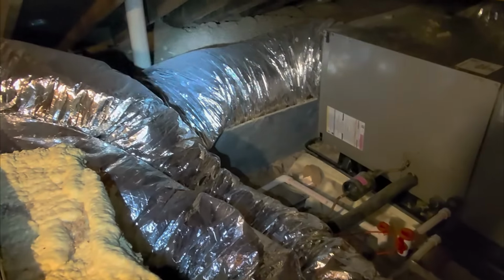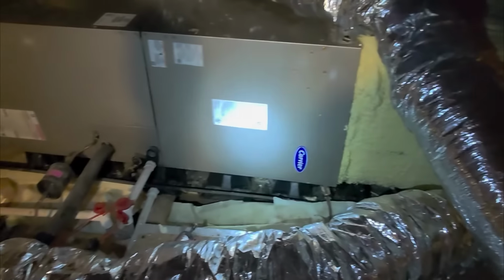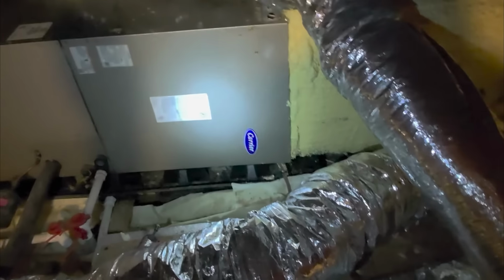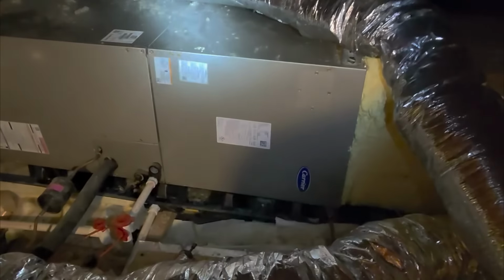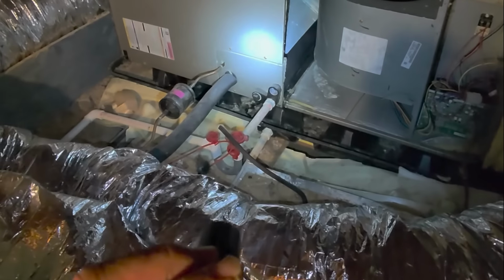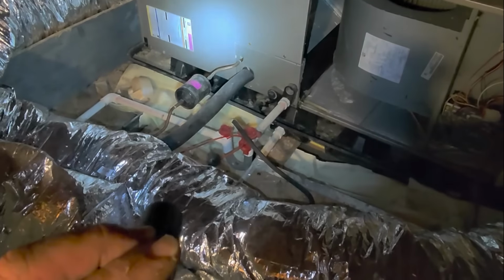And one of the best things that we did here was check static pressure, which you can check right on the Infinity Touch thermostat, and it tells you. Let's take a look inside the hood. All right, I just turned off the switch. I don't want the system to error out with a static pressure issue. Blower wheel looks clean. Bottom looks okay. Coil looks okay. We're gonna get some condensate drain treatment spray and spray the internal condensate pan and a little bit of the condensate tubing leaving, and have a nice day here. All right.